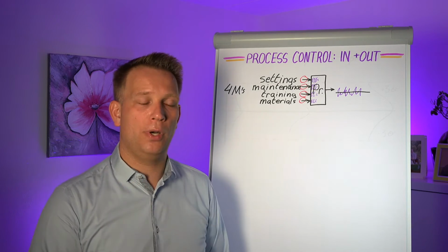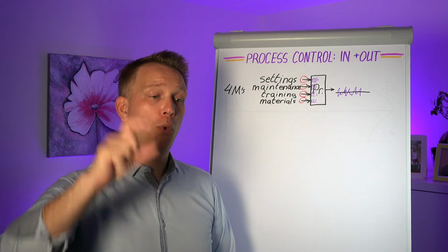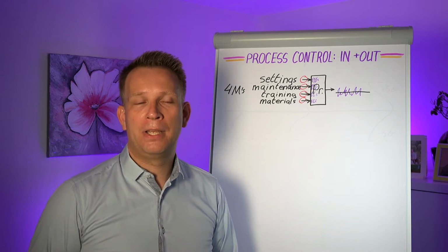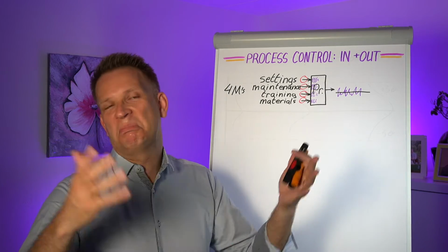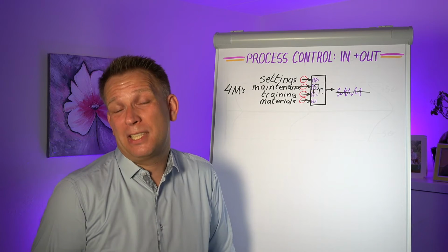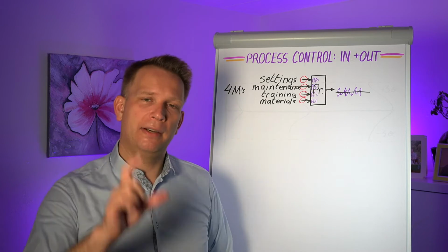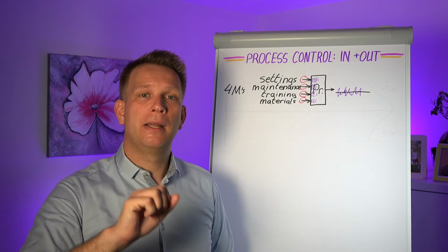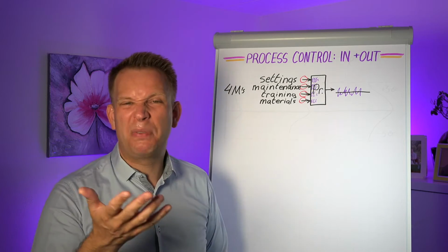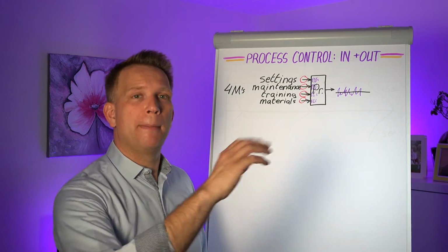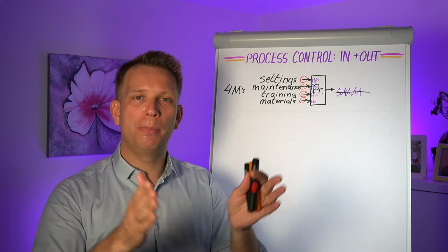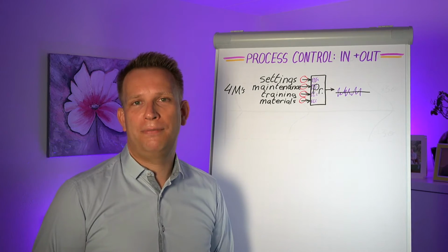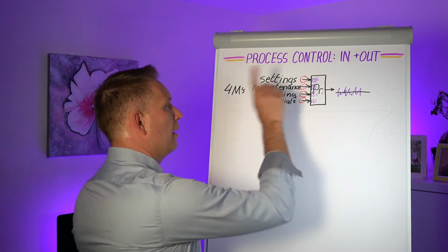But the thickness of a roller, it should be more than 52 millimeters. So a new roller might be 54 or 56 millimeters, and then there's some wear and tear, and at some point it gets a bit thinner, and as soon as it hits 53, for instance, you put in a maintenance order to make sure that it will be replaced before it hits 52. That too is 1 point, right?